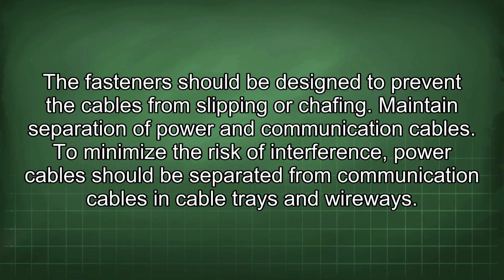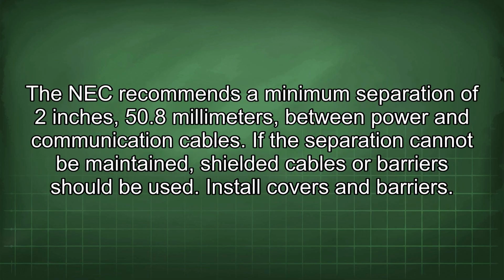Maintain separation of power and communication cables. To minimize the risk of interference, power cables should be separated from communication cables in cable trays and wireways. The NEC recommends a minimum separation of 2 inches (50.8 mm) between power and communication cables. If the separation cannot be maintained, shielded cables or barriers should be used.